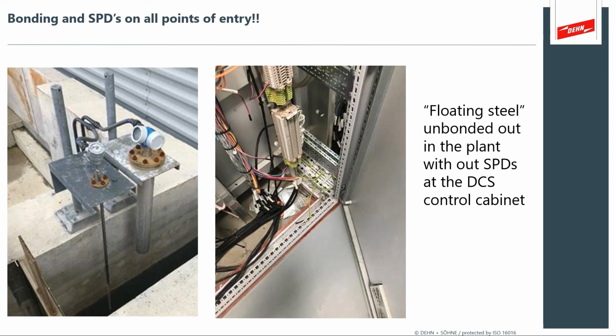This is a couple of photographs that I've seen at electrical sites, and this is quite literally my pet peeve. Floating metal that is not bonded. So in this photograph to the left, you see some metal structures that are supporting things like flow transmitters. And if you're able to see in enough detail, there's actually no electrical earthing on these metal struts. So if there are electrical surges in this circuit, this metal is unbonded and will in fact produce even more ground potential rise.